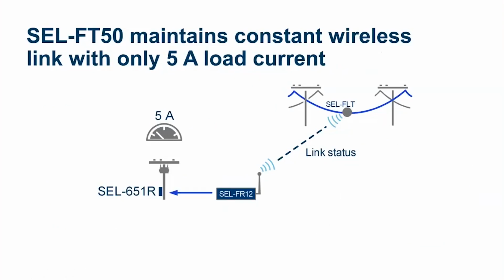If the load current is less than 5 amps, it can still detect a fault in such a condition, but it's going to take a little longer for the fault information to reach the receiver than the 2 milliseconds that we talked about. So if the load is less than 5 amps and you have a fault current which is more than 400 amps, then it could take the transmitter up to 16 milliseconds to send the information to the receiver. So again, you need to have load current above 5 amps for proper or fast working of the setup.